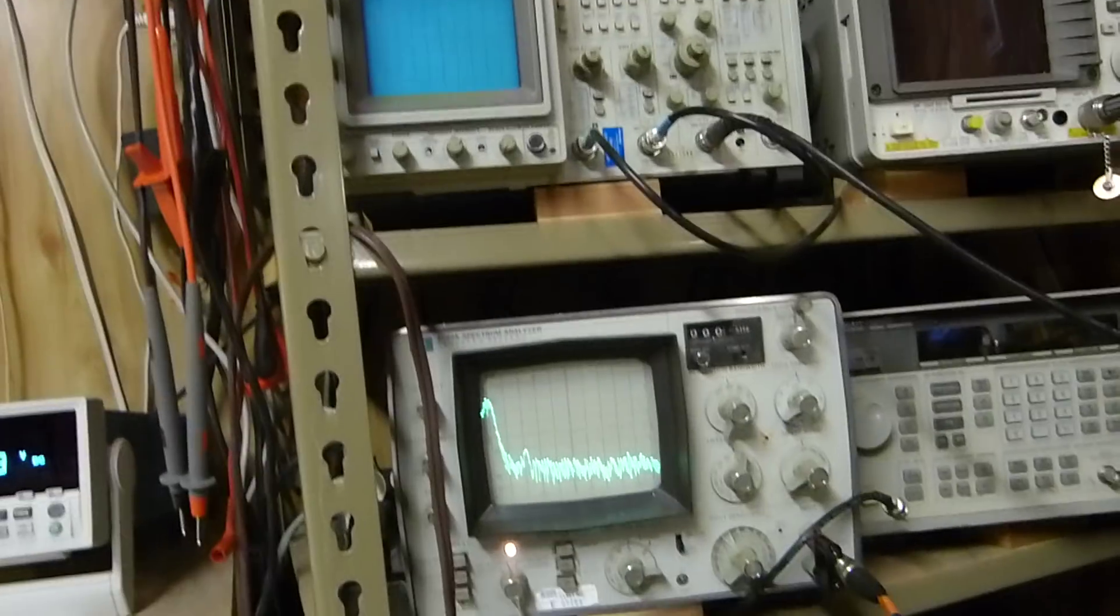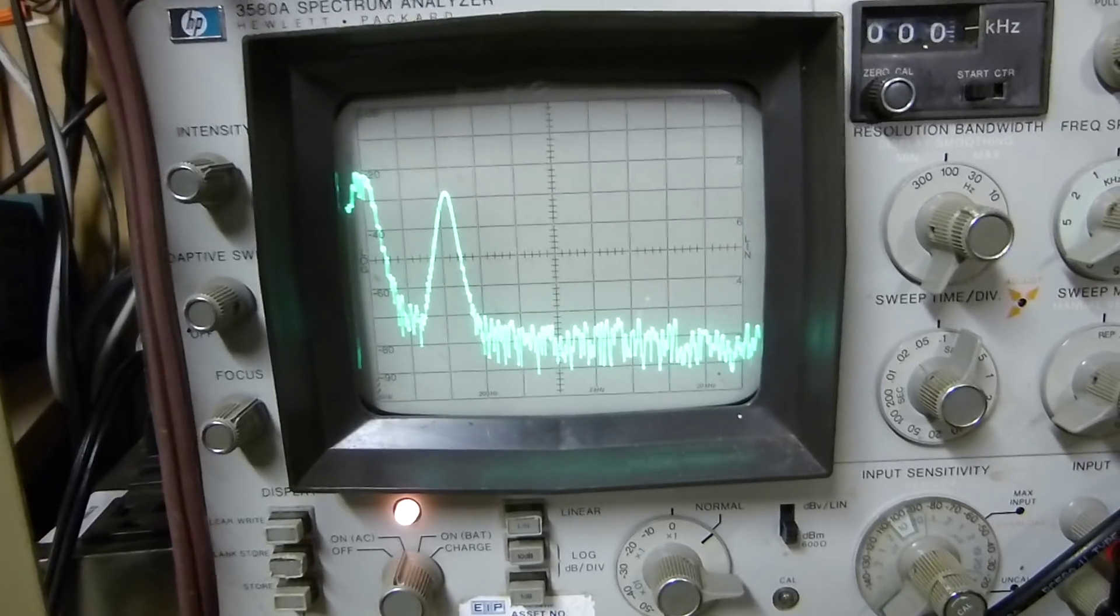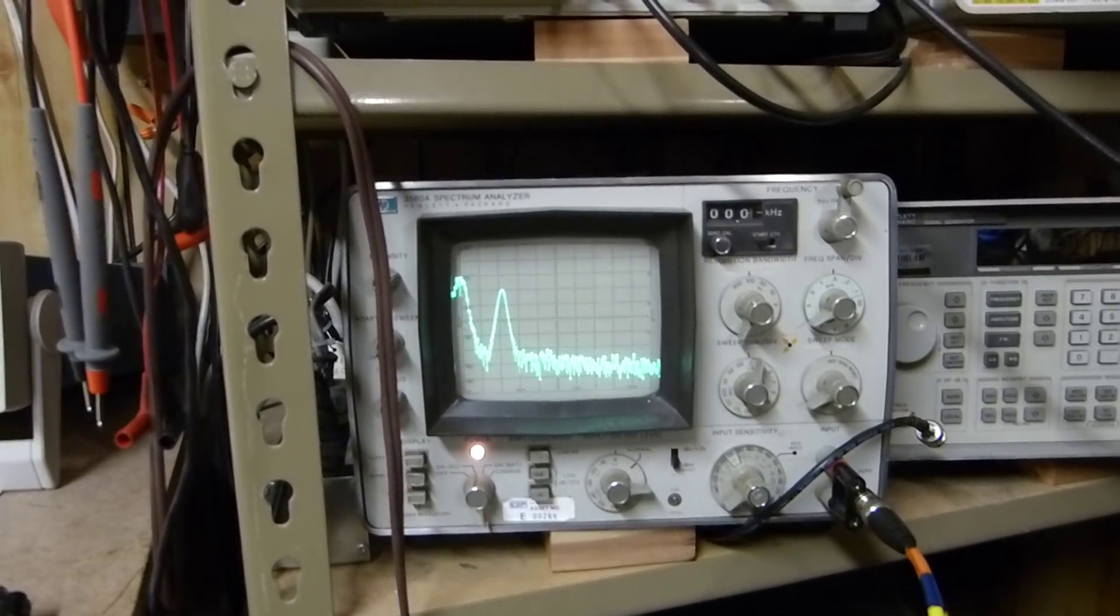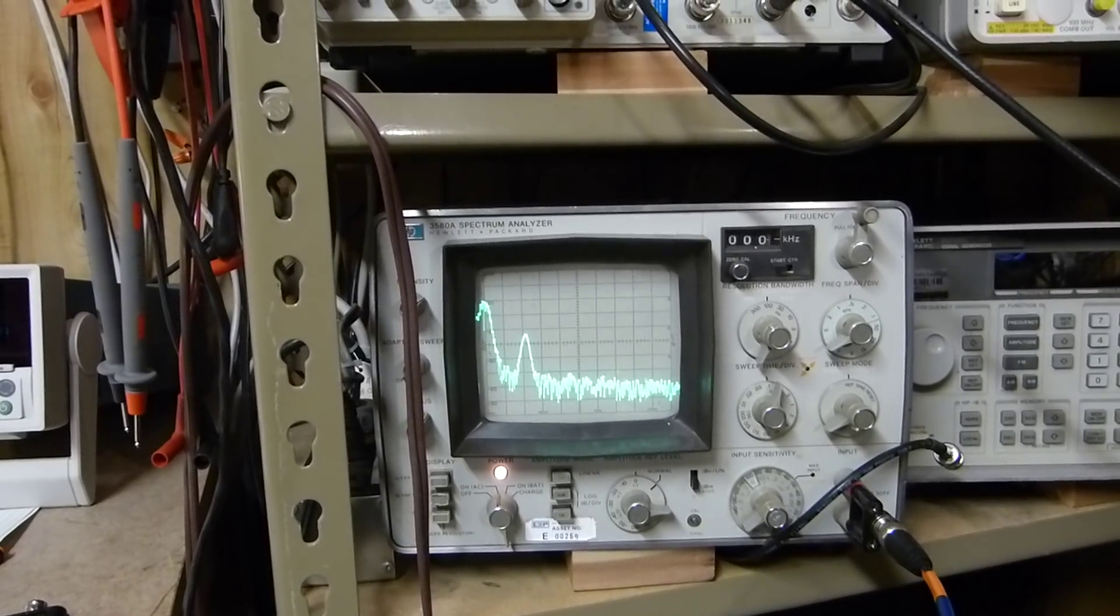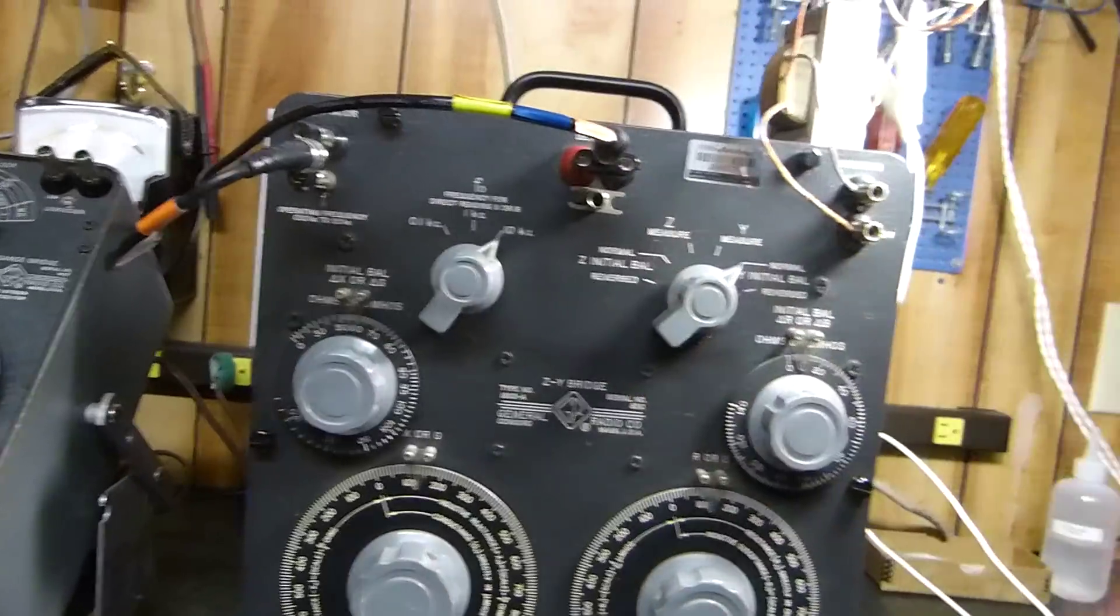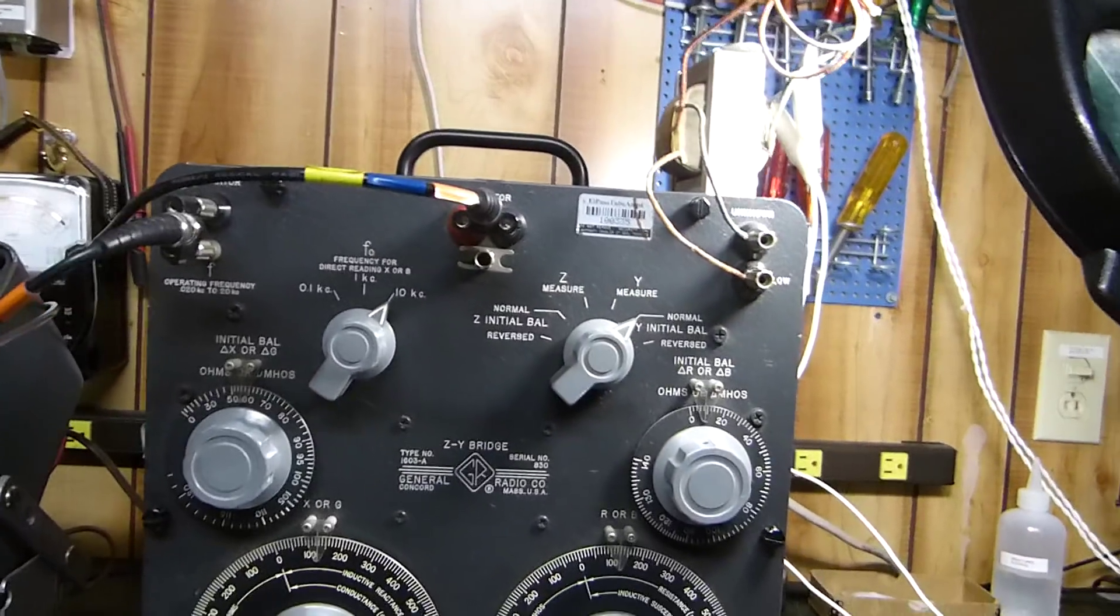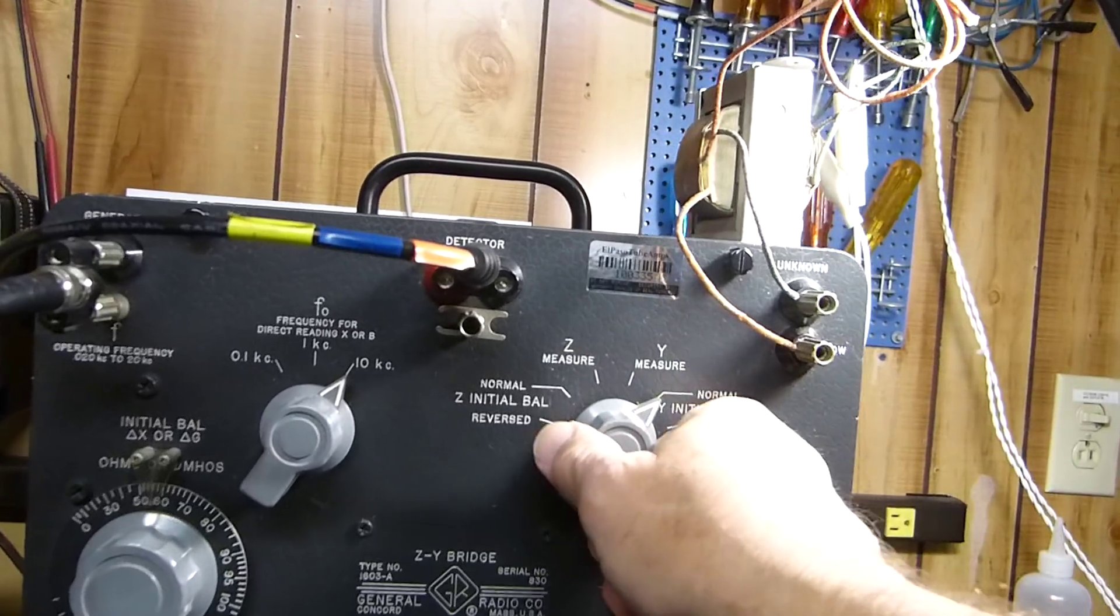I'll just turn this ever so slightly and watch what happens. See, out of balance now, way out of balance. So now I've got to turn it back and get it back in balance as best I can. This is a very tiny signal. It's easy to go past it. Wow, I got lucky there. So I got it nulled again. You go through these two and null so that you're nulling out all of the reactances and resistances and capacitance and inductance, the whole nine yards, so that this bridge is perfectly balanced.